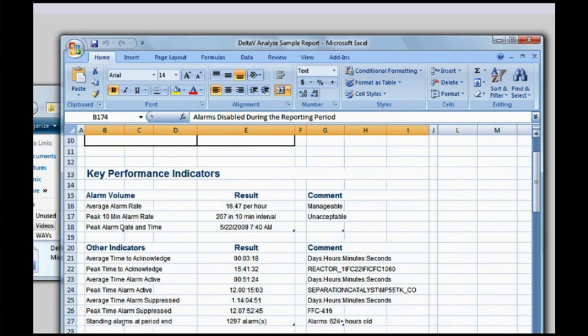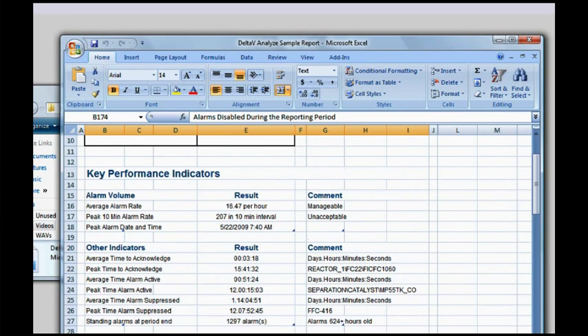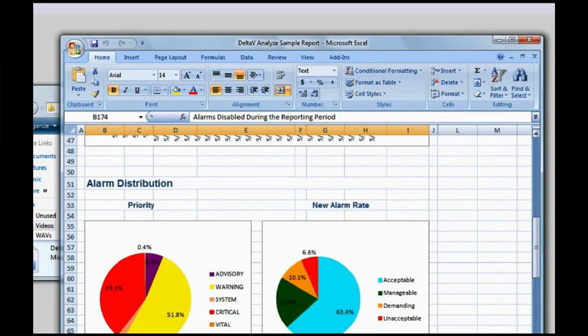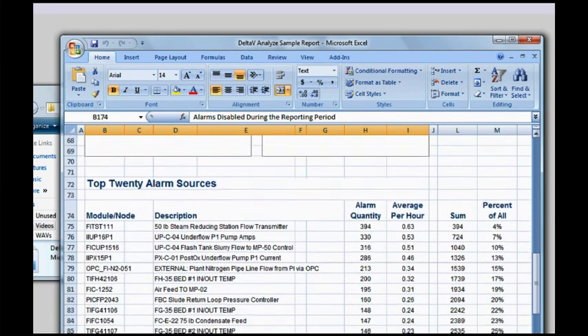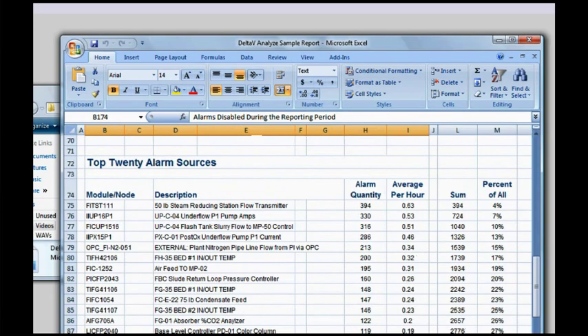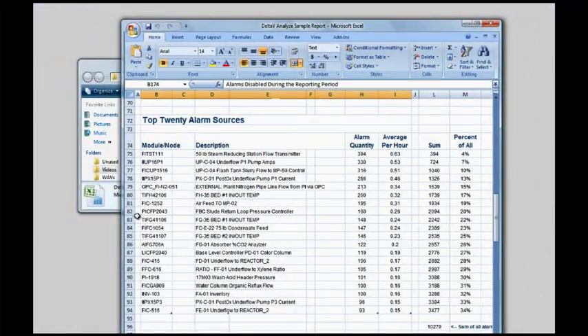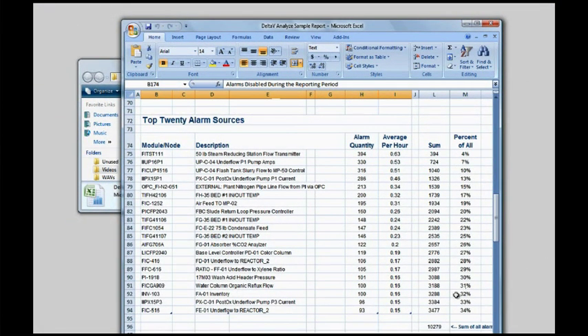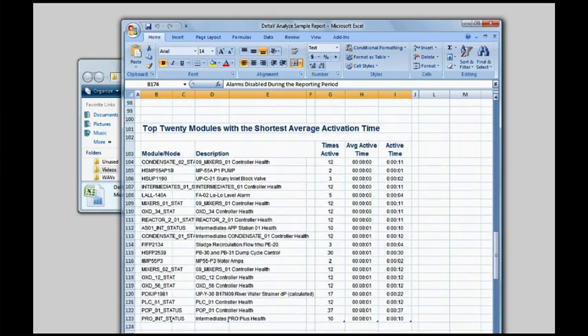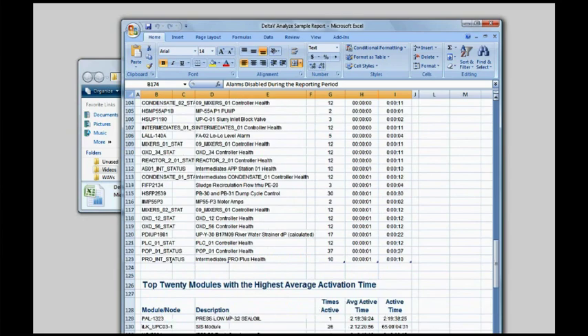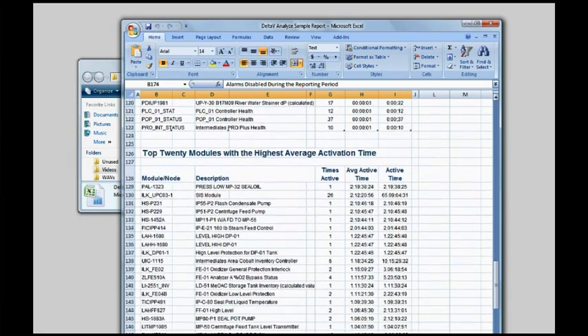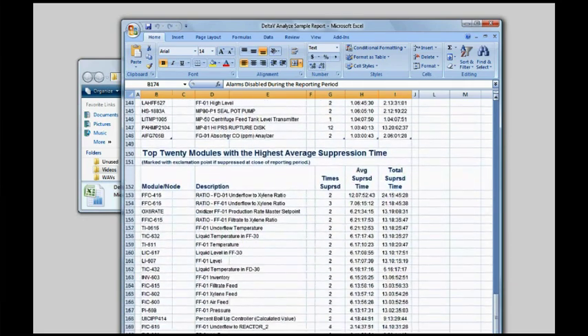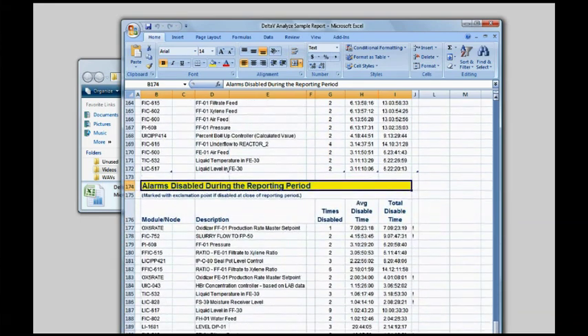Here are your key performance indicators. A quick view of the timeline, followed by some priority and rate distributions. And then what follows is very powerful. What we have here are our nuisance alarms identified for us. This first one shows us the alarms that contribute the most alarms. You'll notice that quite often just a small number of sources will contribute the vast majority of all the alarms in your plant. This particular list here allows you to identify alarms that are active for very brief periods of time, fleeting and chattering alarms. Another list to identify stale alarms, and yet more lists to identify alarms that are frequently suppressed or disabled.